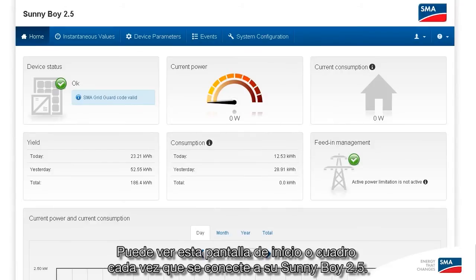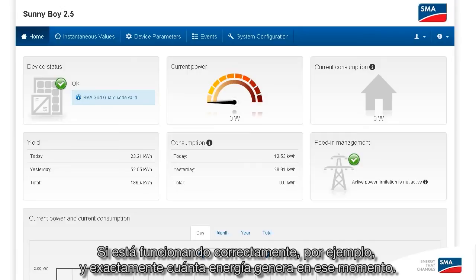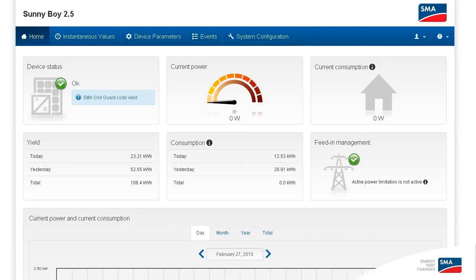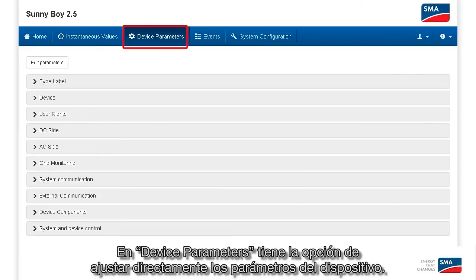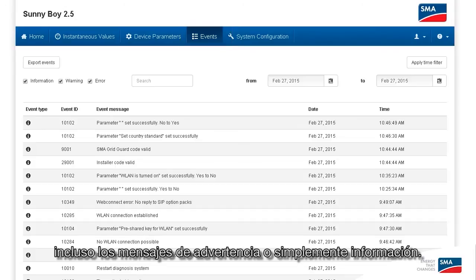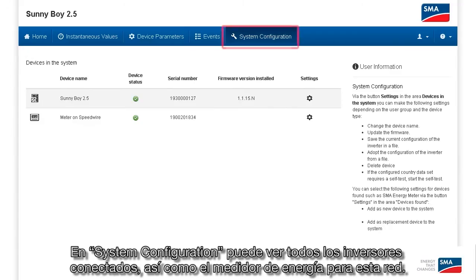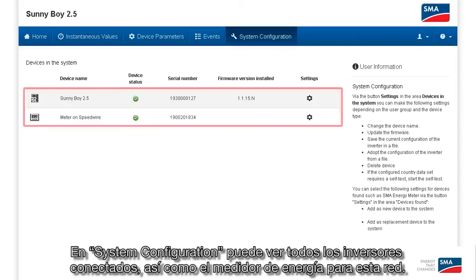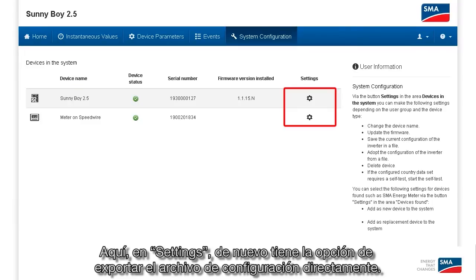You can see this home screen or dashboard every time you connect to your Sunny Boy 2.5. Here you can see at a glance all the important data from your inverter — whether it's running properly and exactly how much power it is generating at the time. Under Instantaneous Values, you can see instantaneous values in more detail. Under Device Parameters, you have the option of adjusting the device parameters directly. Under Events, you can see everything that has happened with your inverter recently — any warning messages or just information — and you can also export these as a CSV file. Under System Configuration, you can see all the connected inverters as well as the energy meter for this network. Under Settings, you again have the option of exporting the configuration file directly.